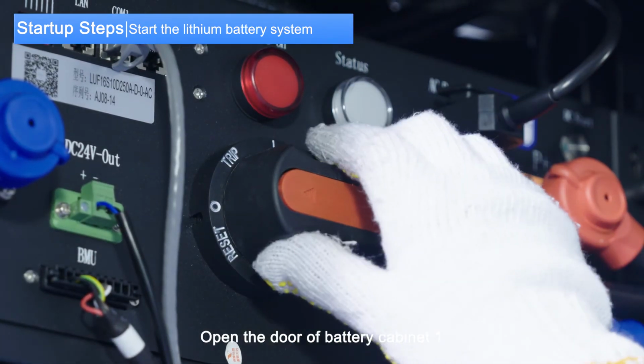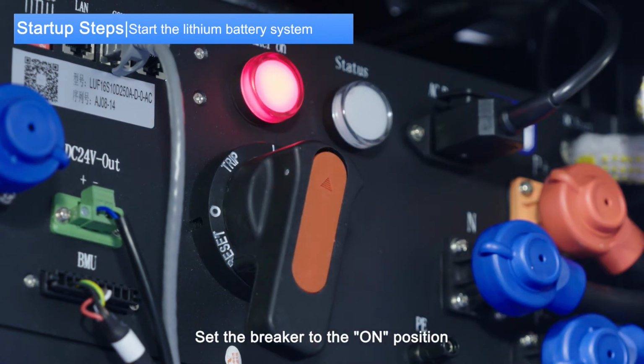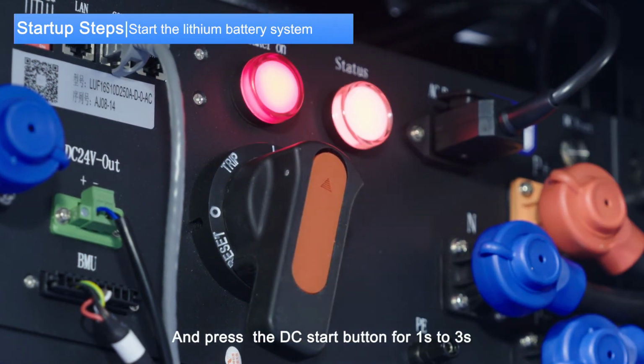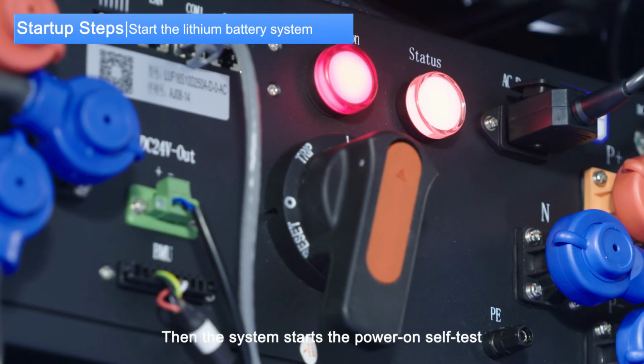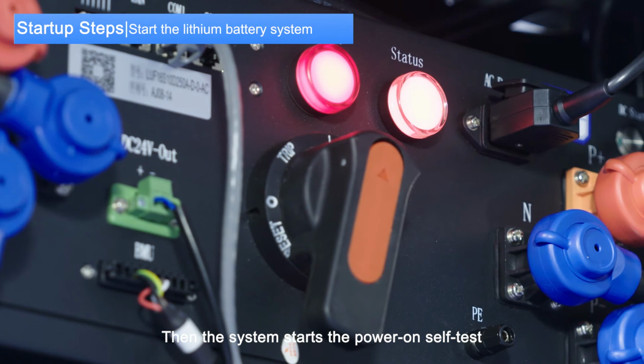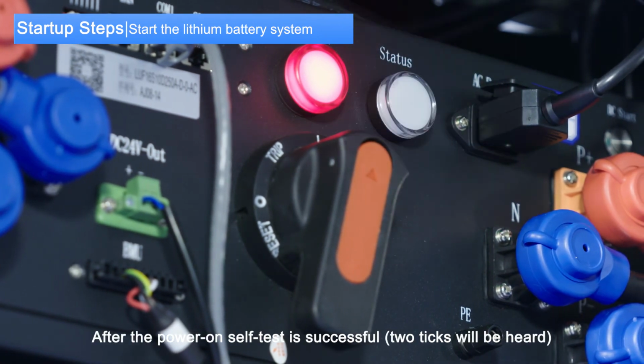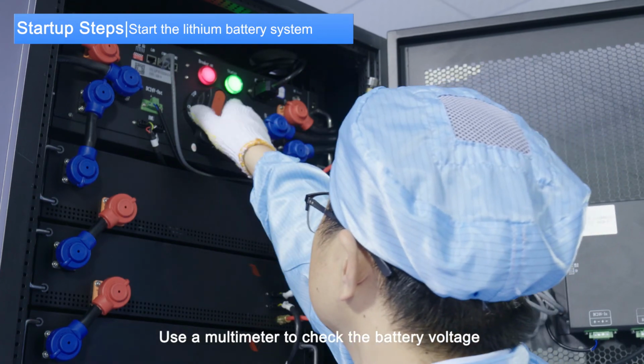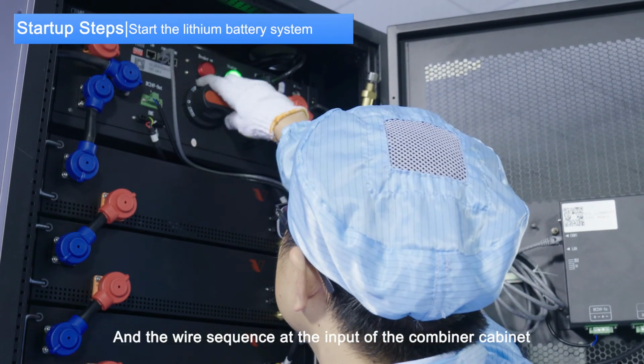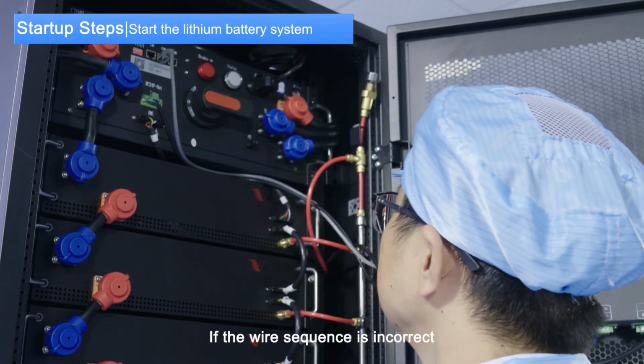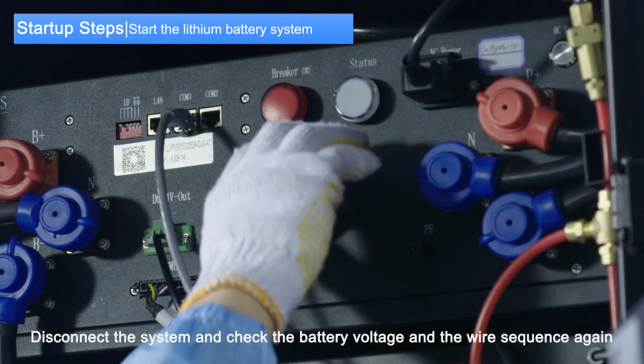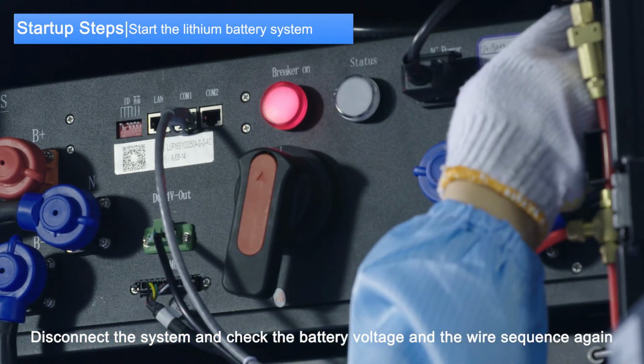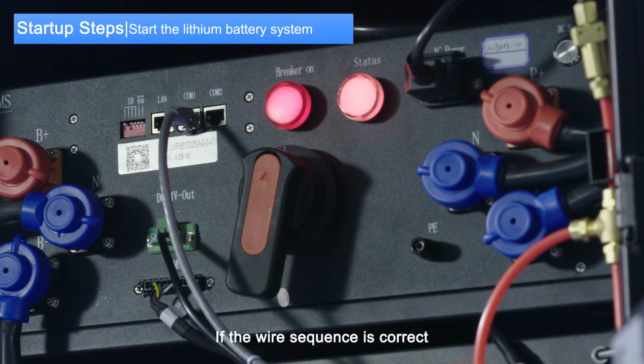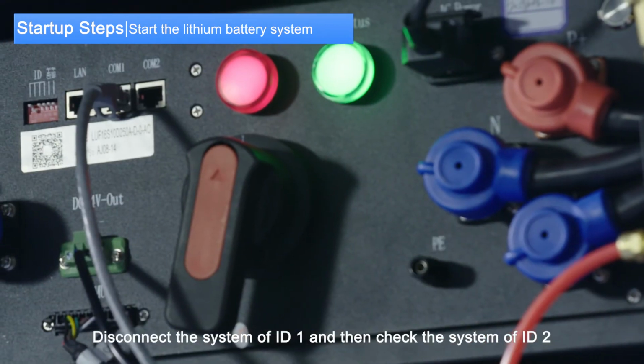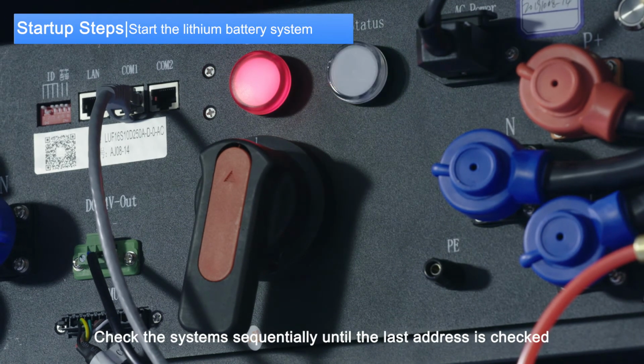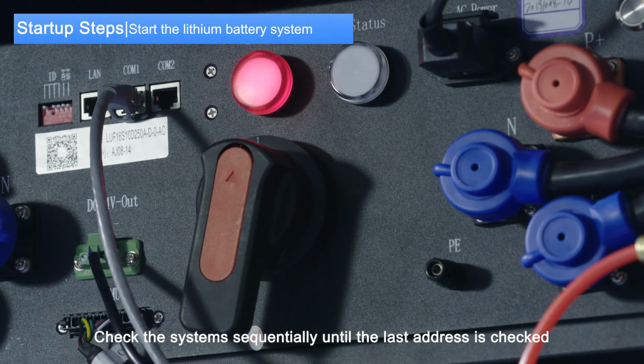2. Open the door of battery cabinet 1. Set the breaker to the on position and press the DC start button for 1 second to 3 seconds. Then the system starts the power on self-test. After the power on self-test is successful, 2 ticks will be heard. Use a multimeter to check the battery voltage and the wire sequence at the input of the combiner cabinet. If the wire sequence is incorrect, disconnect the system and check the battery voltage and the wire sequence again. If the wire sequence is correct, disconnect the system of ID 1 and then check the system of ID 2. Check the system sequentially until the last address is checked.